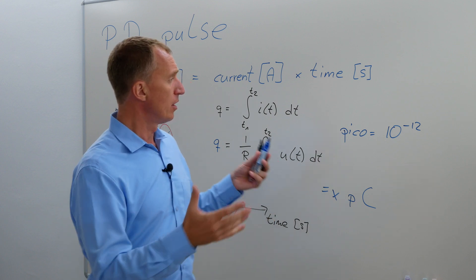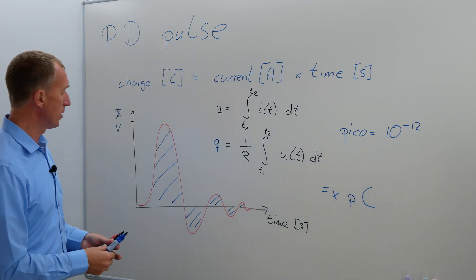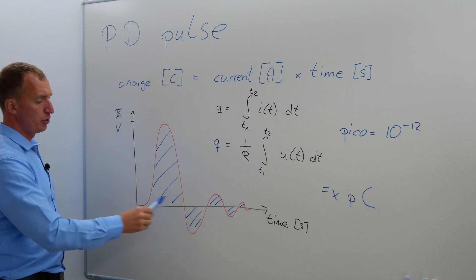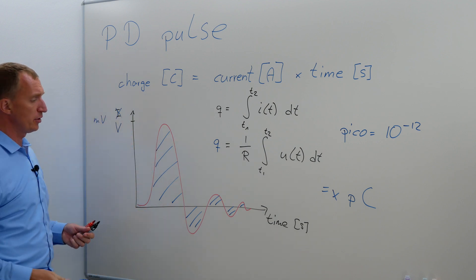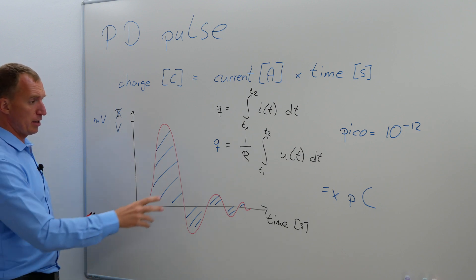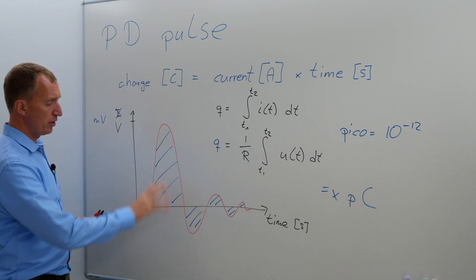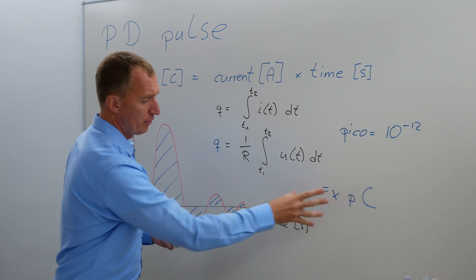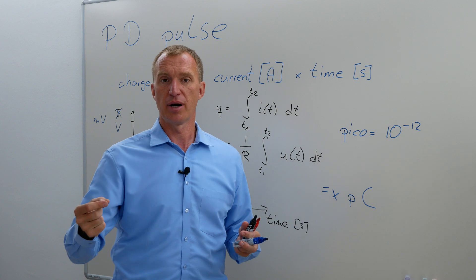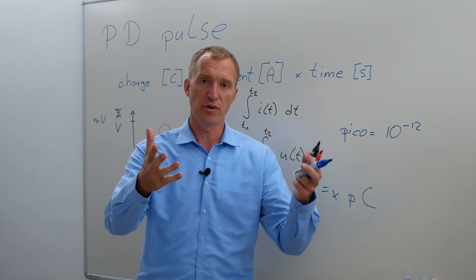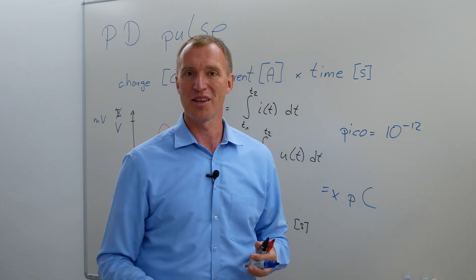So to sum up, a partial discharge pulse, the electrical pulse looks a little bit like that. We do an integration, otherwise we would only have a millivolt value. But the standards usually talk about a charge value. So we do the area below the curve, we come up with hopefully a picocoulomb value. And we do this for every single pulse happening. So thank you very much for watching and hopefully see you in another video.